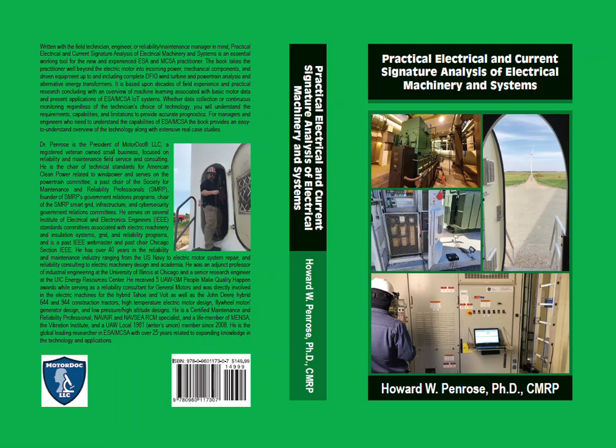Contrary to popular belief, the original purpose of motor current signature analysis and electrical signature analysis was not the detection of rotor bar defects in induction motors. In fact, the original purpose was to evaluate the mechanical components of the electric motor and driven equipment of a motor-operated valve in the nuclear power industry, including lubrication issues, mechanical wear in the gearbox, valve defects, bearing defects, power quality, and the electric motor, using the air gap of the motor as the transducer. ESA provides a non-load dependent, repeatable method for evaluation from a remote location, such as the motor control center.